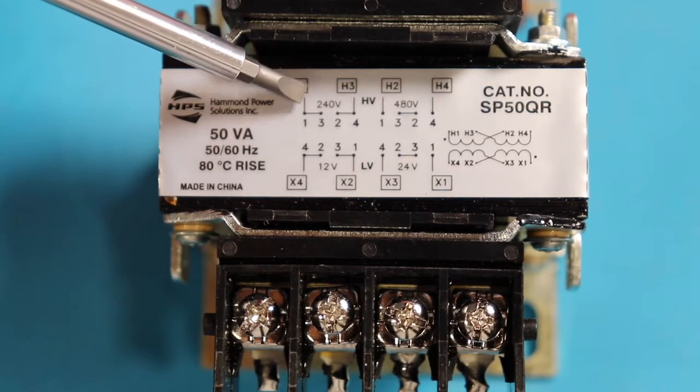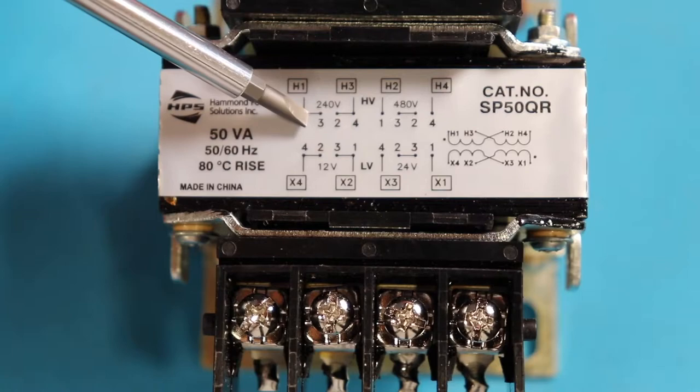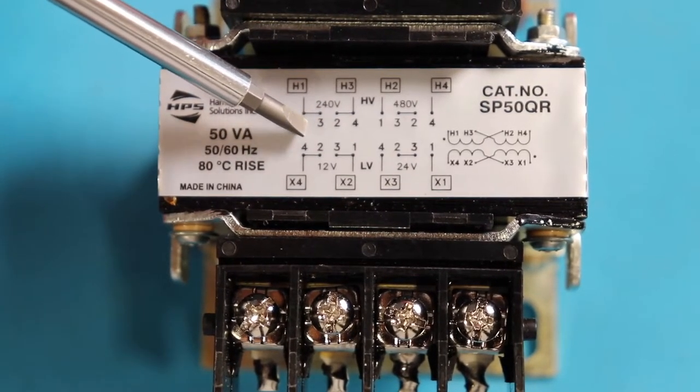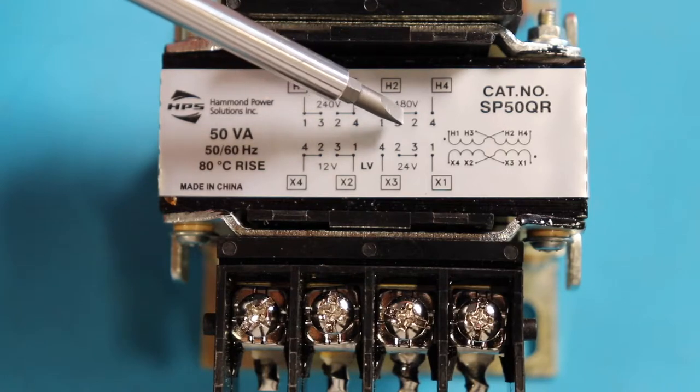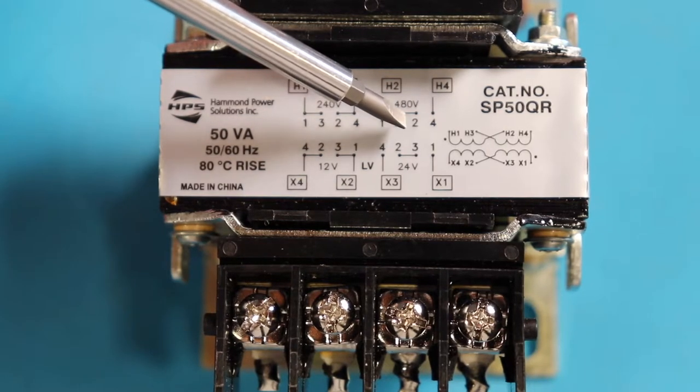Now to achieve 240 volts, we got to add jumpers in here. These lines indicate jumpers, 1 and 3 and 2 and 4. If we want to do 480 volts, we got to insert a jumper between 3 and 2.